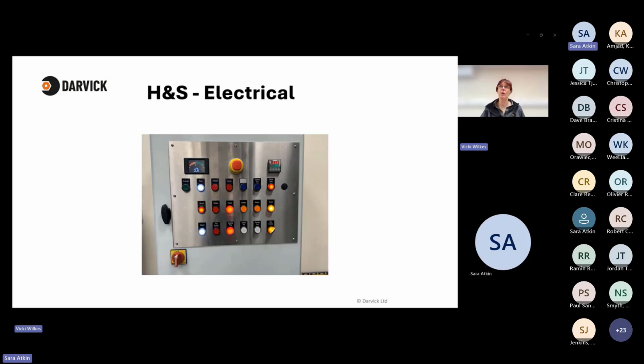So you can buy components, load cells and solenoid valves, that are classed as intrinsically safe. These are basically designed to prevent any sparks or heating that could ignite an explosive atmosphere, even if there's a fault, even if something goes wrong. The downside to that is that these tend to be more expensive. You've got limited choice. They could be on longer lead times. And even though we buy those where possible, where it's practical, you still can't design a complete system. You can't have your entire controls and interlocks made out of intrinsically safe items.